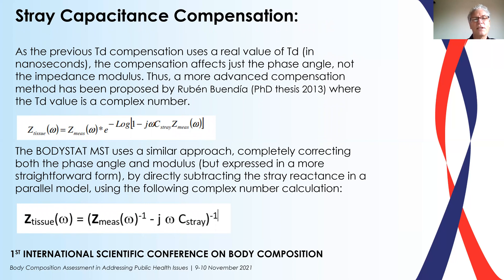Bodystat's MST device uses a similar approach, completely correcting both the phase angle and modulus, but expressed in a more straightforward form. By directly subtracting the stray reactance in a parallel model using a complex number calculation, we get a much truer representation of the stray capacitance, which we can then compensate.